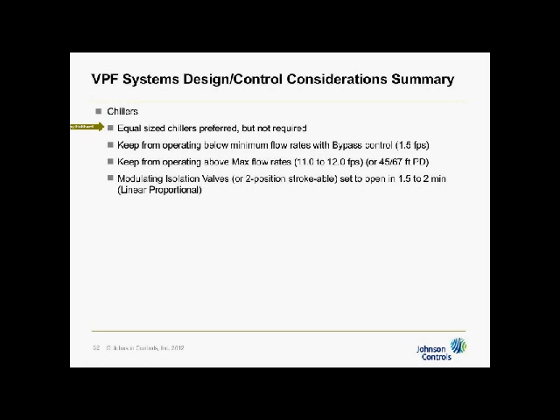What's more important than having equal-sized chillers is having equal pressure drop across each chiller. So they can be different sizes. It just makes the math a little more complicated when you're trying to do calculations in balance. And it's also more difficult to keep them in balance when you've got folks going around cranking balancing valves and not putting them back in the right place. So it's better, but you don't have to.